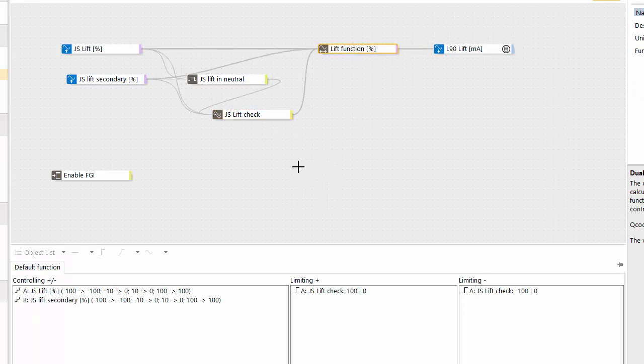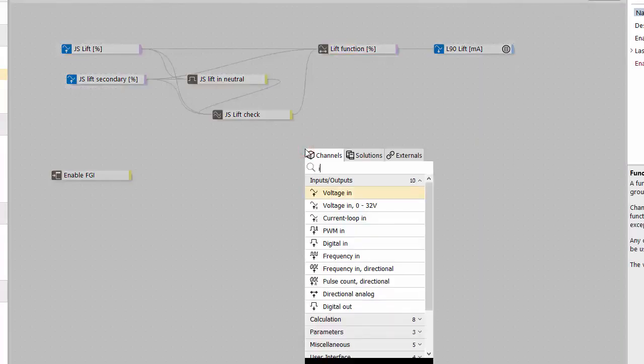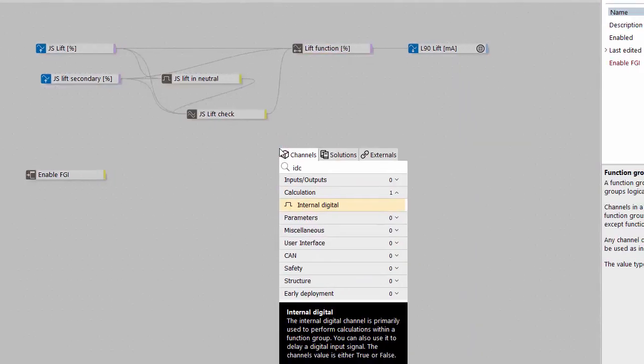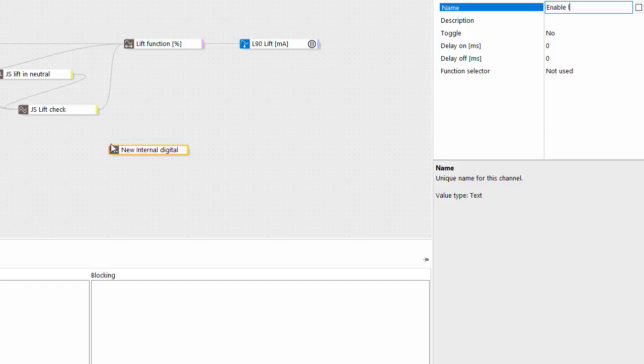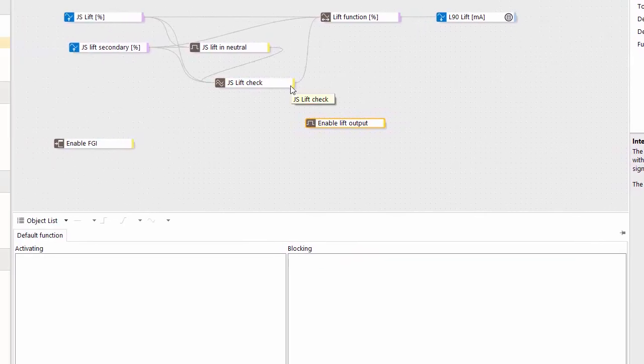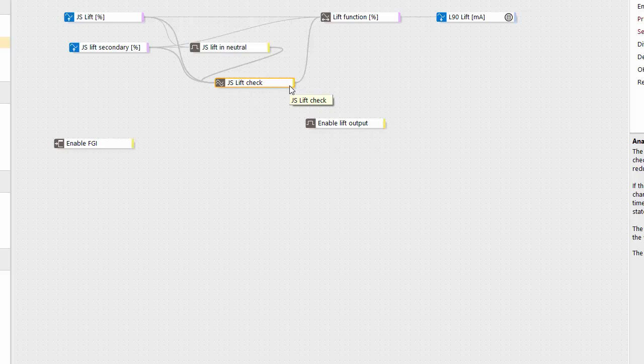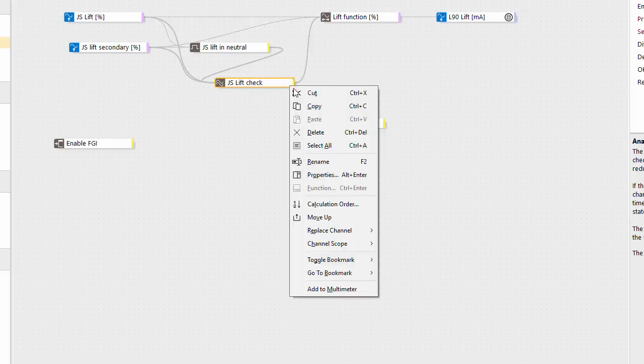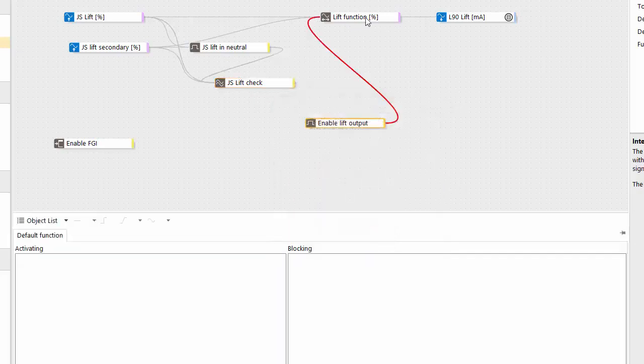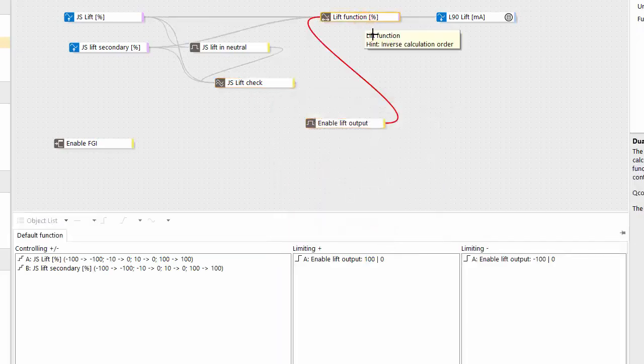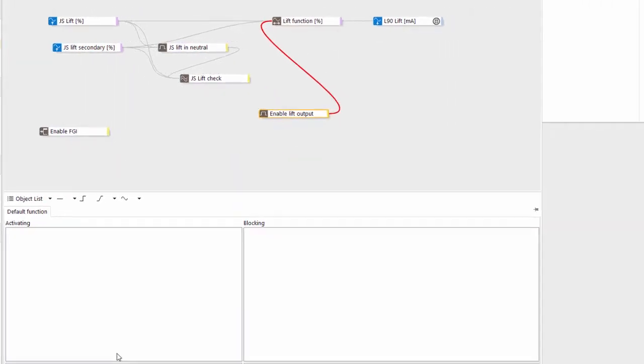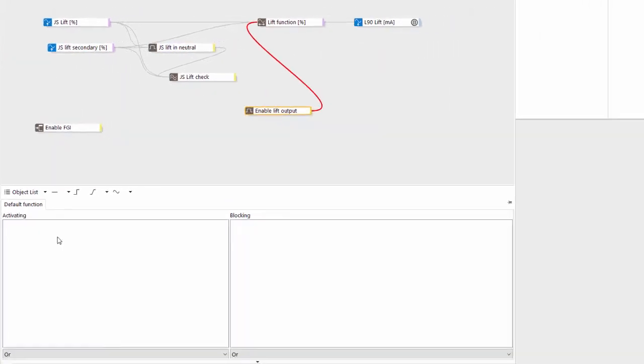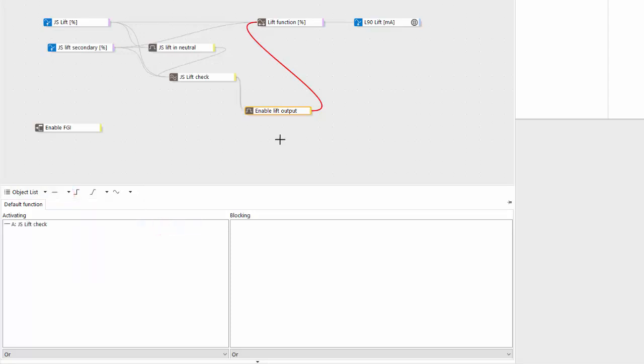We have the joystick lift check connected to the lift function now and I'd want to insert this enable condition in here. So let's use one internal digital in between. So adding an internal digital, call it enable lift output, and here we can use a trick called replace channel. So replacing this with enable lift output replaces those references over here.